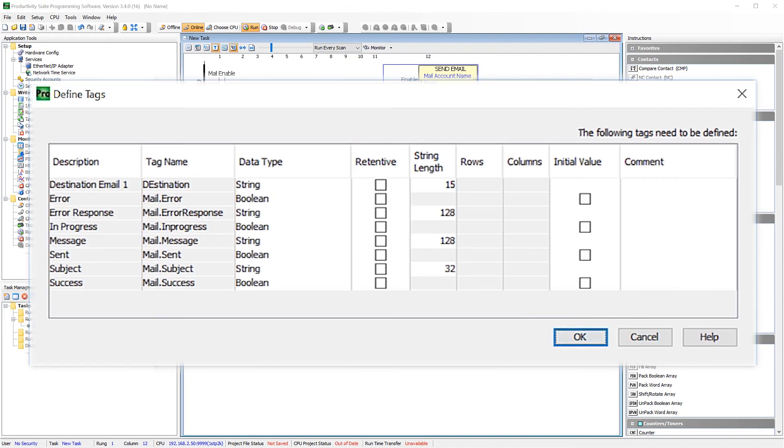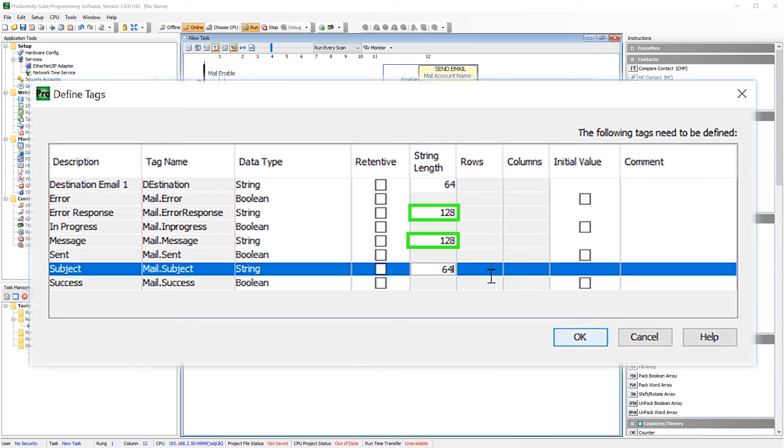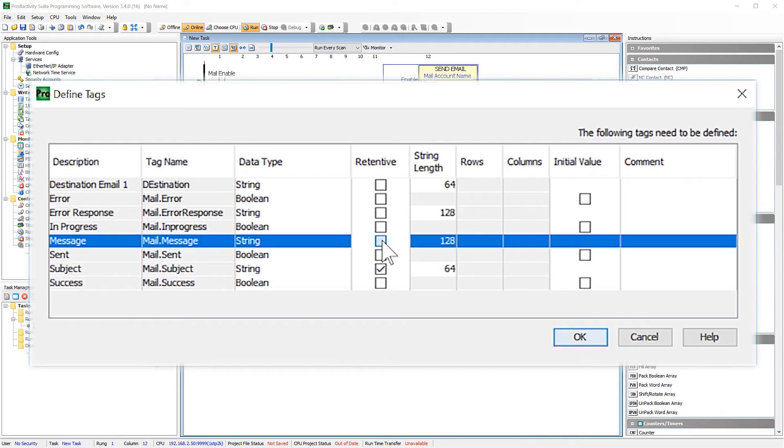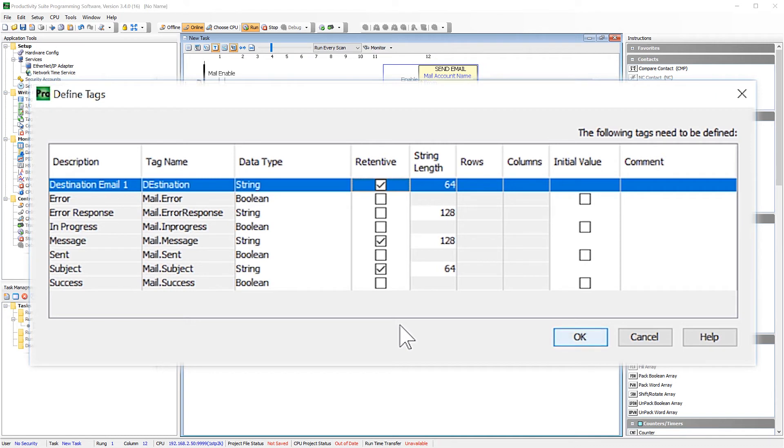I would advise changing all your strings to at least 64 characters. Now for these, I would go ahead and go with the max number of characters. And I would also advise to make sure that these are retentive. Now one of the things I want you to make note of, both the message and subject are strings. And the max characters for these are 128. You will need to keep this in mind when creating your email messages.